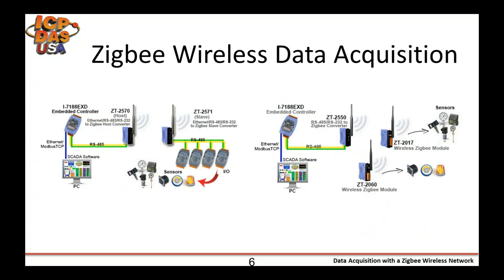Which brings us to data acquisition with a ZigBee network. Data acquisition is the process of sampling real-world physical information and converting those samples into signals that an electrical device can understand. Our data acquisition devices support a wide range of inputs and outputs, both digital and analog — RTD, thermistor, thermocouple voltage, etc. The data acquired can be logged and displayed in the control center and/or sent to a PLC for M2M applications, as you can see with the gauges, alarms, and start/stop commands.